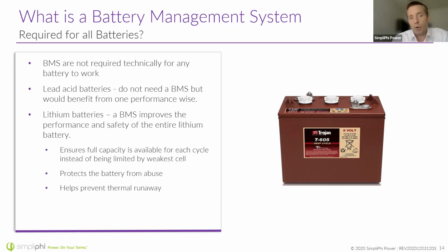Lithium batteries now default to kind of 48-volt for home battery backup, so you have 16 cells in series. It's very necessary to maintain the balance between those stacks of cells inside the battery. It ensures you get the full capacity of the battery. By actively monitoring and adjusting the individual voltages of those stacks to make sure the system is operating properly, we can ensure we get the longest lifetime out of the battery, and also get that full capacity to be able to use it.